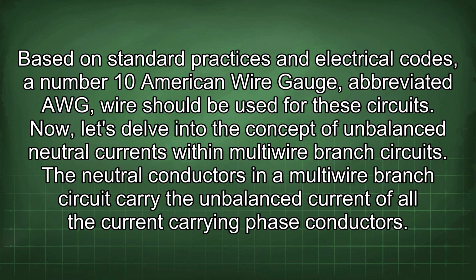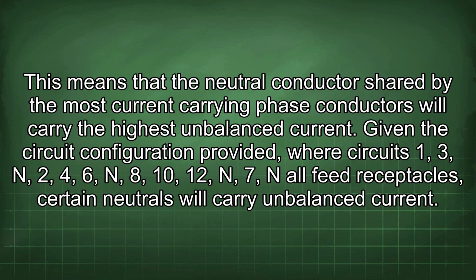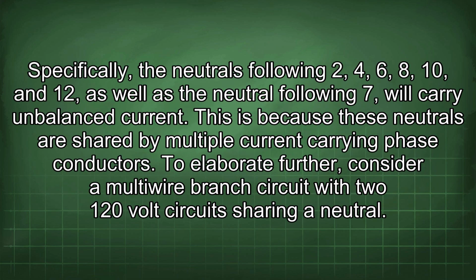The neutral conductors in a multi-wire branch circuit carry the unbalanced current of all the current-carrying phase conductors. This means that the neutral conductor shared by the most current-carrying phase conductors will carry the highest unbalanced current. Given the circuit configuration provided, where circuits 1, 3, N, 2, 4, 6, N, 8, 10, 12, N, 7, N all feed receptacles, certain neutrals will carry unbalanced current. Specifically, the neutrals following 2, 4, 6, 8, 10, and 12, as well as the neutral following 7, will carry unbalanced current. This is because these neutrals are shared by multiple current-carrying phase conductors.